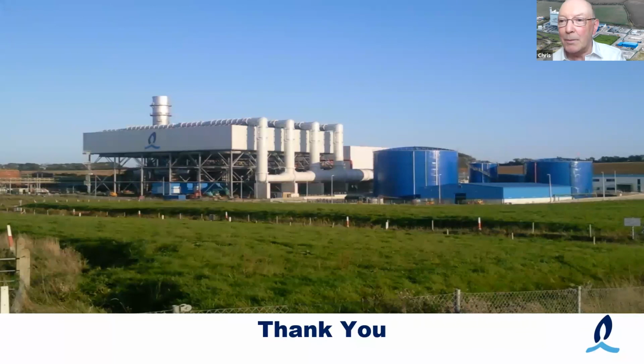Yeah, so the unit will follow grid instructions, but the output will move around that instruction as well. So let's say it's at 390 megawatts and the frequency is below 50 hertz, the unit will govern to attempt to correct that itself. So it has a 4% droop setting on the governor. That's fairly common across units like Whitegate.